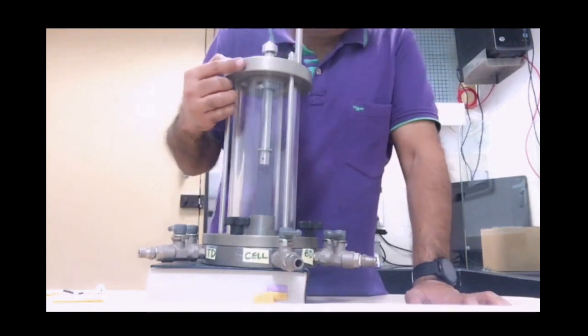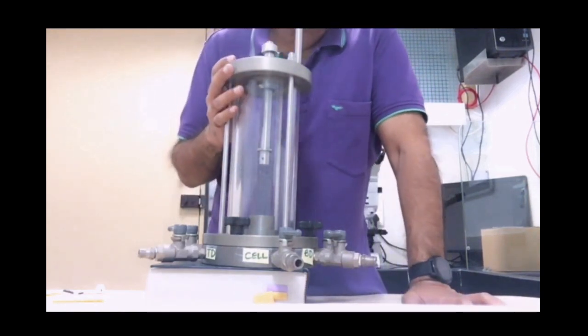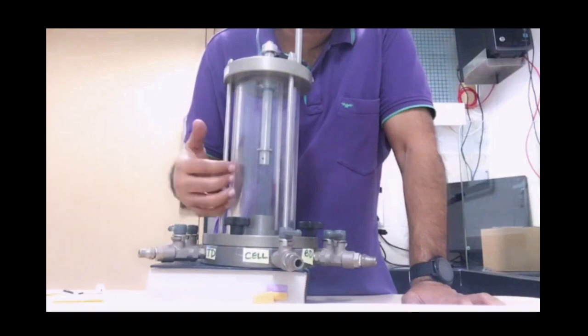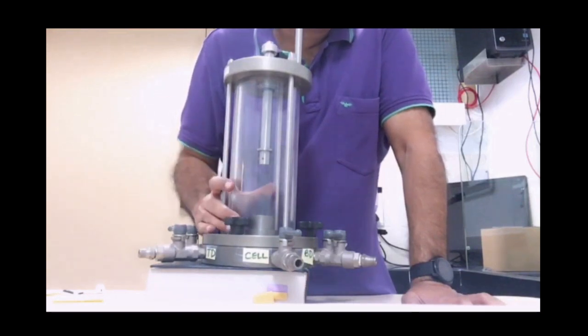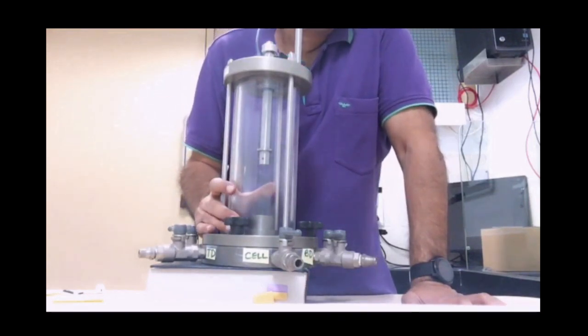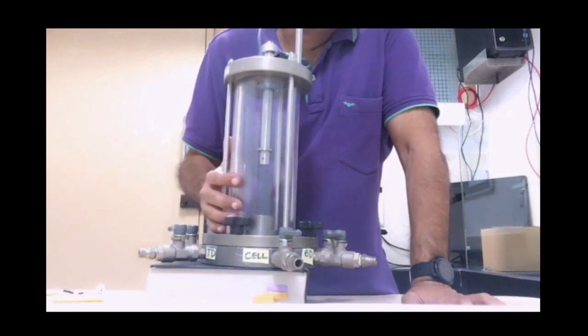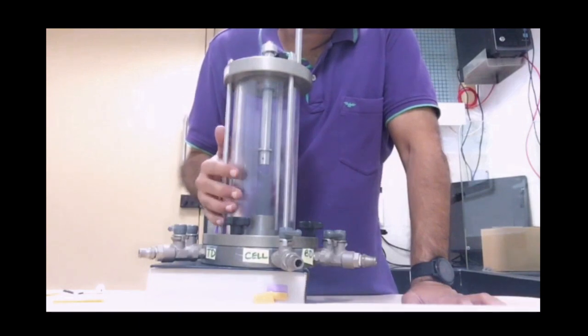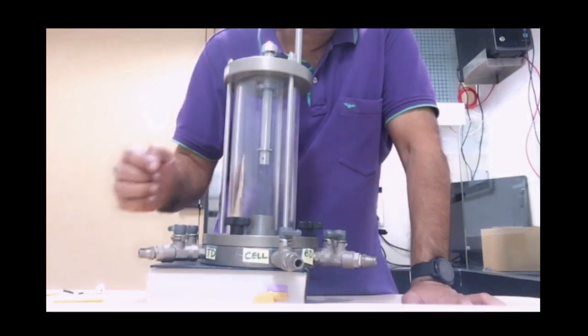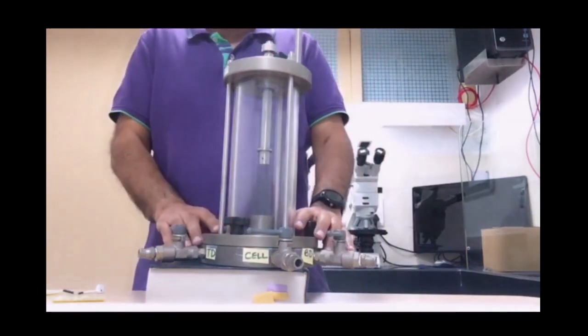The equipment itself, which is used to pressurize this, can have a working pressure of about 800 kPa if I'm using air. So you have a limit to how much you can go. Of course, let me look at the other procedure.